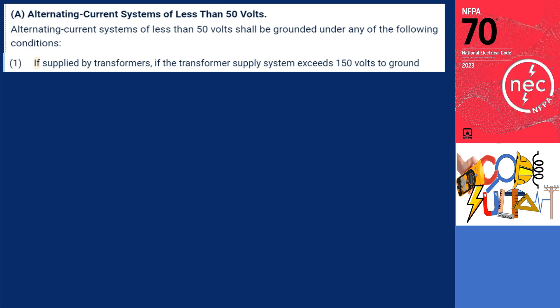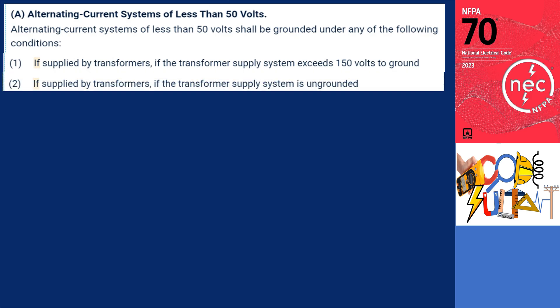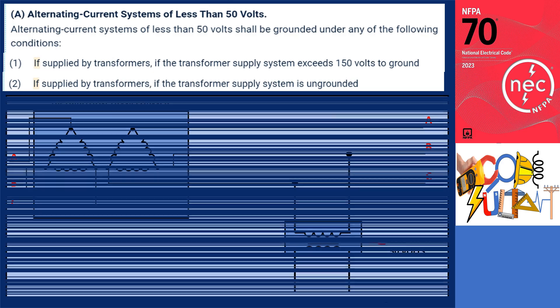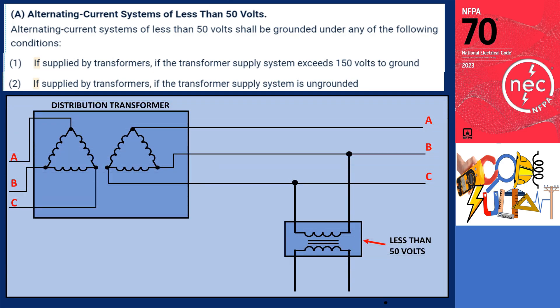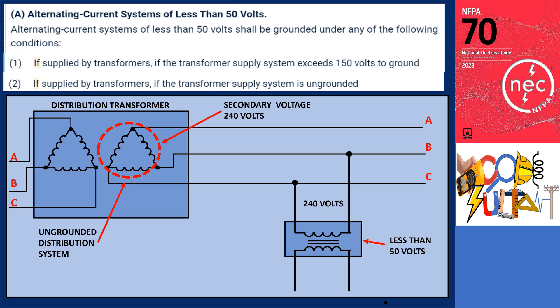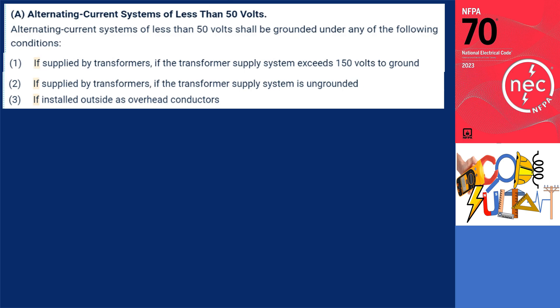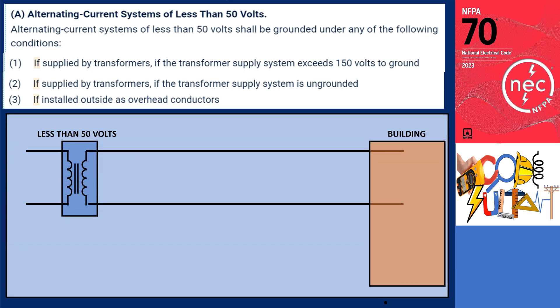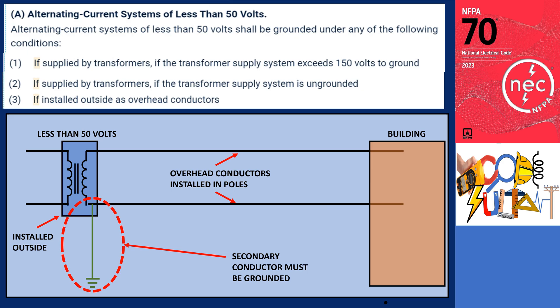For condition 2, if supplied by transformers, if the transformer supply system is ungrounded — for example, a delta-connected system, which is an ungrounded distribution system. In this case, regardless of the voltage, it is necessary to connect one of the transformer's secondary conductors to the ground. For the third condition, if the alternating current system is installed outside as overhead conductors and the transformer secondary conductors enter the building from outdoors as overhead conductors, the system must be grounded. This condition applies when the system operates at a voltage of less than 50 volts and the conductors are installed on poles outside the building.